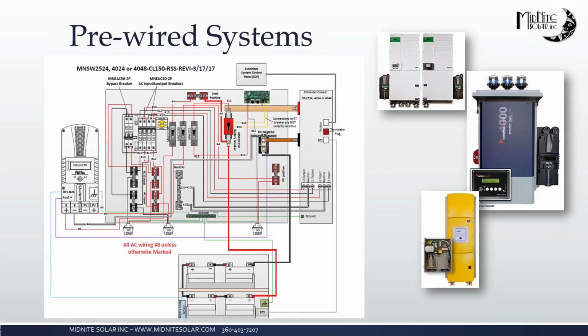They'll run a battery of tests on this system, high power tests, everything, and they will sign a checklist with all this test procedure, and they will include this wiring diagram with the system. This is a more simplified one for an SW, but if it was a quad stack or a large system, this may be a multi-page drawing. All the drawings will have a customer connection page, and you can't see my air quotes here, but we have what we call customer connection pages for AC and DC and communications. So it makes it very easy for the end user or the dealer that's installing this to look at that and say, okay, this is where this goes and this is where that goes. So we try to make it pretty easy for you.